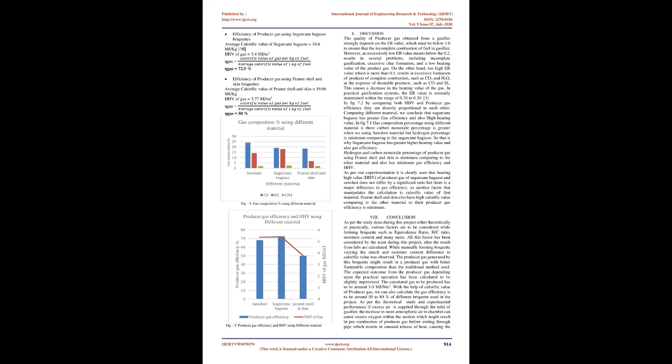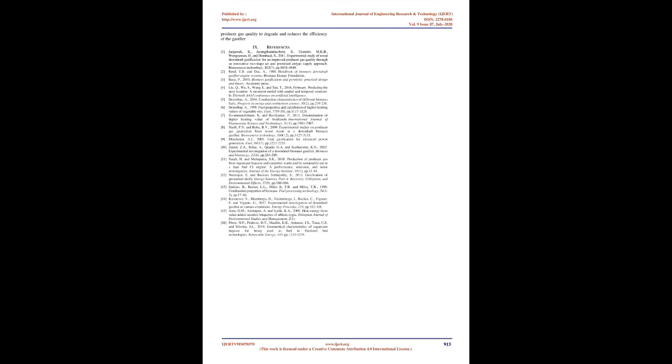Discussion: The quality of producer gas obtained from a gasifier strongly depends on the ER value, which must be below 1.0 to ensure incomplete combustion of fuel in the gasifier. However, an excessively low ER value below 0.2 results in several problems including incomplete gasification, excessive char formation, and a low heating value of the product gas. On the other hand, too high an ER value which is more than 0.5 results in excessive formation of products of complete combustion such as CO2 and H2O at the expense of desirable products such as CO and H2. This causes a decrease in the heating value of the gas. In practical gasification systems, the ER value is normally maintained within the range of 0.20 to 0.30.